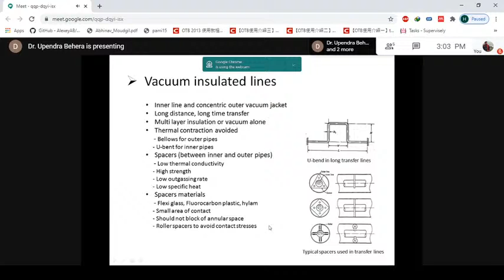Okay. Then spacers of low thermal conductivity material support the inner pipe within the outer pipe; you need low thermal conductivity materials of high strength, low outgassing rate and low specific heat. The spacer materials are generally plexiglass, fluorocarbon plastic, hylum or bakelite, and they should be designed so that the point of contact is minimized, so that less heat transfer takes place. Though these are all low thermal conductivity materials, the point contact should still be as low as possible, and these are the different configurations.